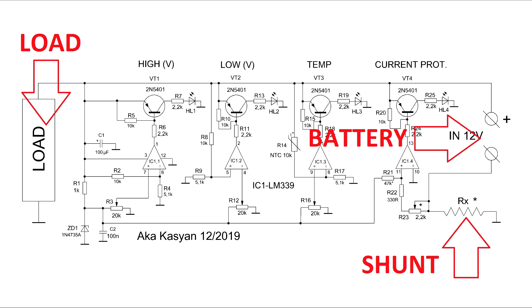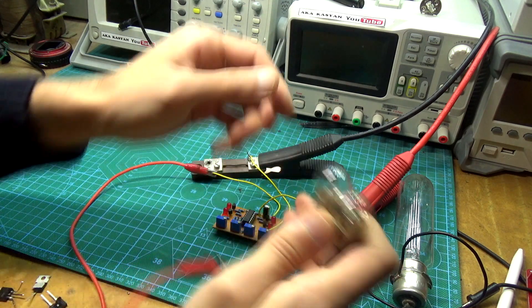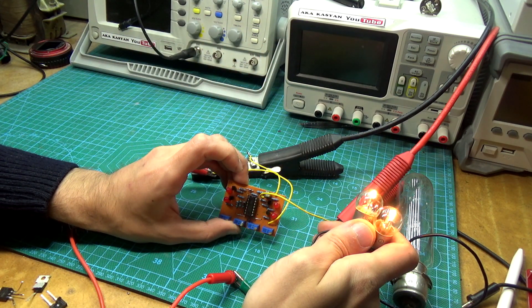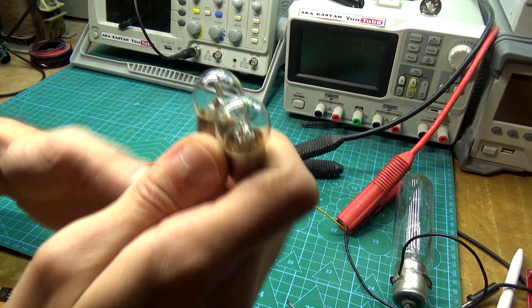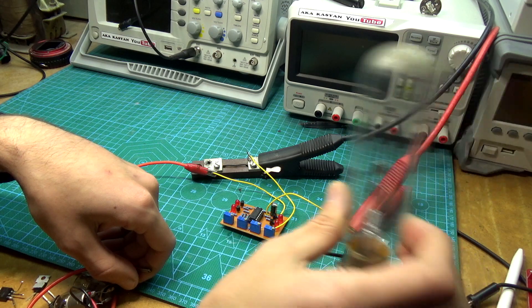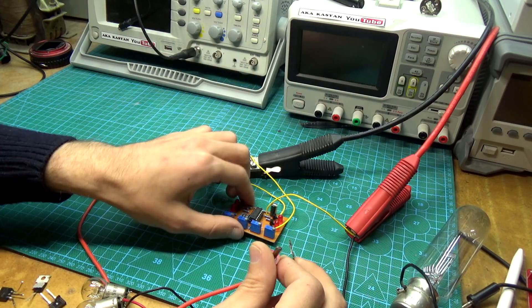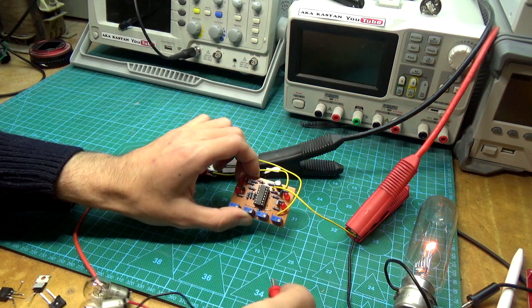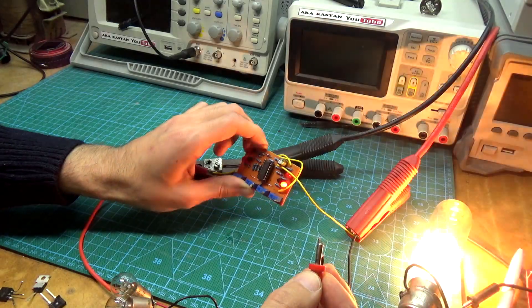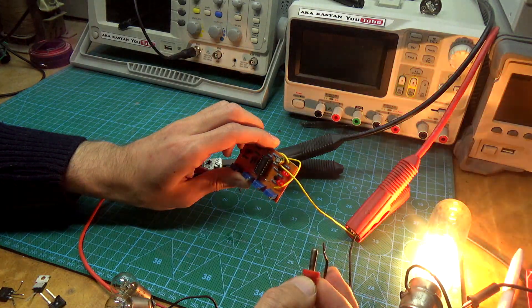Next, connect everything as shown. We increase the load until a current in the circuit becomes equal to value at which the protection must operate. The current is controlled by an additional ammeter or by measuring the voltage drop across the shunt and then, according to Ohm's law, you can calculate what current flows in the circuit. The last option in this case is the most convenient. If you have achieved the required current, simply rotate the fourth tuning resistor until the LED turns on.